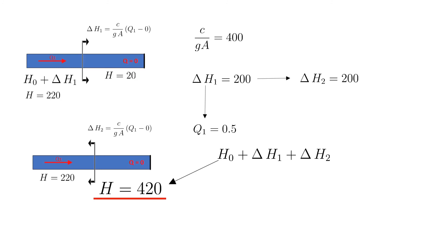It is evident that waves reflecting off dead ends or shut valves can result in high pressures. Be aware that in this example we used an incoming wave of positive 200. If the incoming wave was negative, it would reflect negative thus lowering the pressure head by twice the magnitude of the incoming negative wave. This can often result in formation of a cavity.